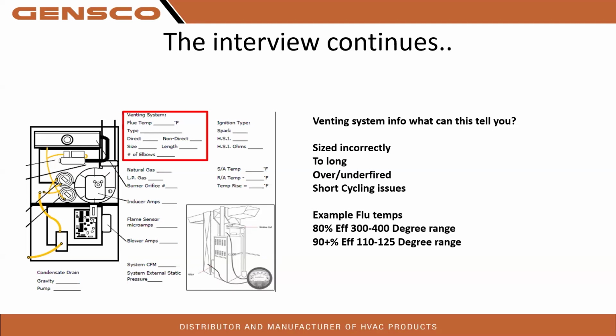So an example of flue temps: 80% efficient, 300 to 400 degree range. That's a good 80% furnace burn temp. 90 plus efficiency, depending on how much of a plus it is, we're going to be between 110 and 125. So we can get a lot of information out of that. Let's say we pull a flue pipe temp out of a 90%er and it's reading 140, and we're getting scaling in the heat exchanger. Well, we don't have a heat exchanger anymore, we have essentially a boiler, right? So we can have some buildup in that secondary heat exchanger we don't want. So that can tell us some stuff, right? So we're collecting data to try to figure out if there's an issue here, whether it be sizing and all that.